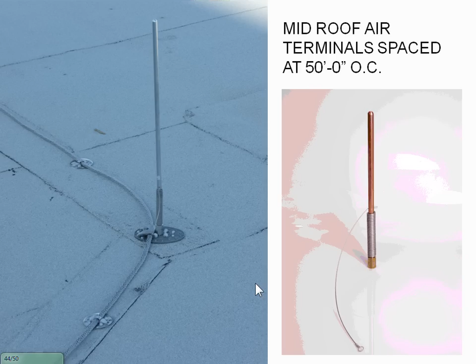The other part of the system is the cable and how to secure it to the building. Once again, you can glue it or screw it to the building. Code states it has to be secured every 3 feet on center. The reason is that a little bit of play in the cable on a windy day can start to move, and it starts to chain react, pulling all the clips out if it's secured every 20 feet on center instead. So we screw it to the copings or glue it down every 3 feet, which holds it in place and the cable won't go anywhere.